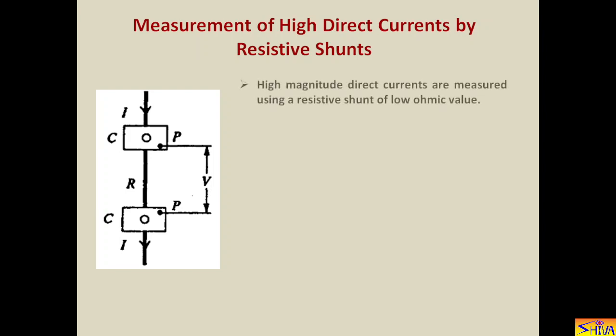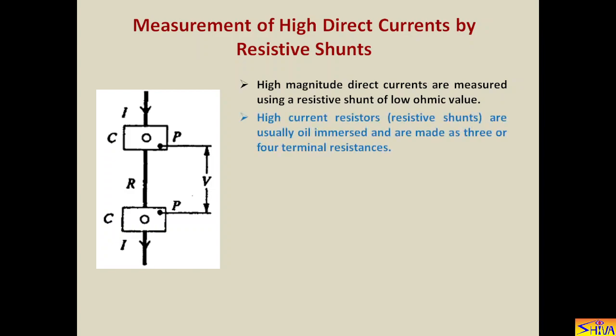The method I am discussing now — measurement by resistive shunt — is useful for AC currents as well as DC currents, but we normally restrict it to DC current only because for AC current we prefer the CT method. High magnitude direct currents are measured using a resistive shunt of low ohmic value. High current resistors are usually oil immersed and made as three or four terminal resistances. These are current terminals CC, and PP are voltage terminals.